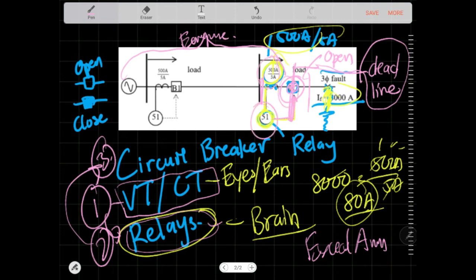So, you need three components. When a fault happens, you're going to say, oh, the breaker opens. No, no, no. You must say, in your exam, you must say that the current transformer, voltage transformer picks up the reading, gives a reading to the relay. The relay takes the input reading and makes a decision based on the relay logic and based on the time delay. Does it activate? How long do I wait to activate? And if it activates, the relay doesn't activate on its own. It sends a signal to trigger the circuit breaker to activate. Then the circuit breaker activates and boom, you clear the fault.